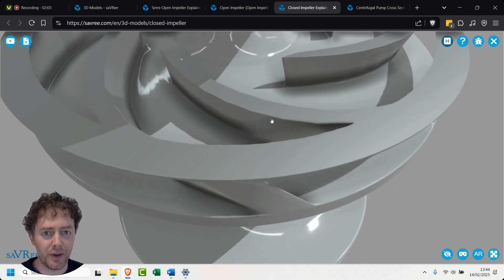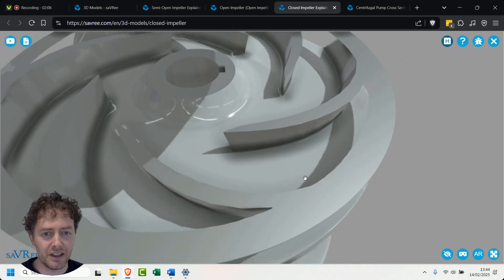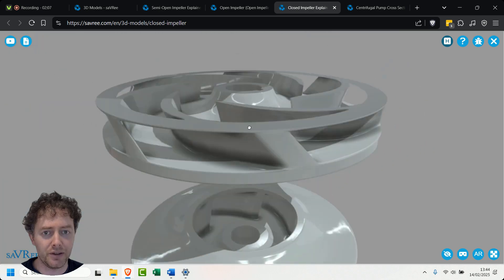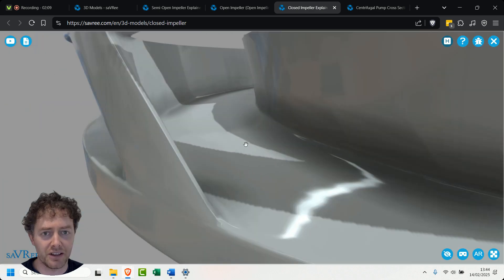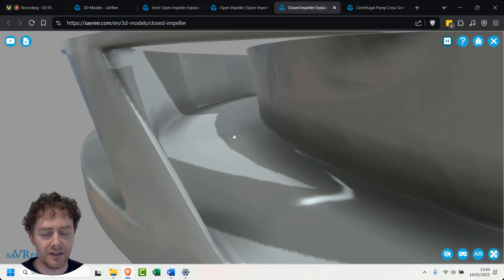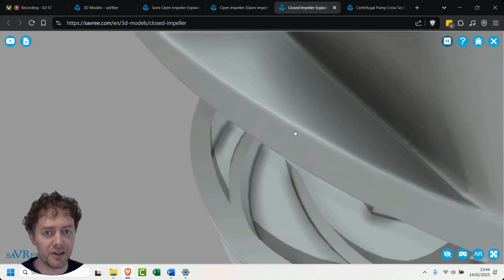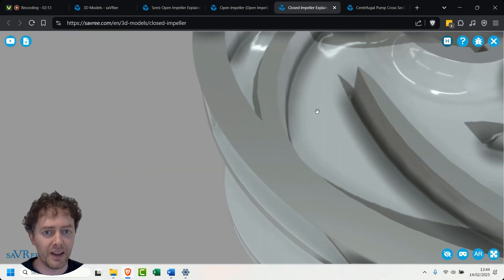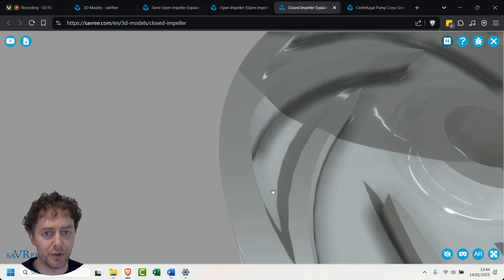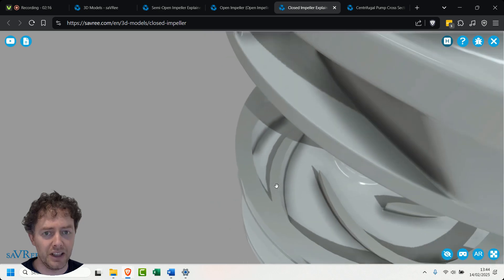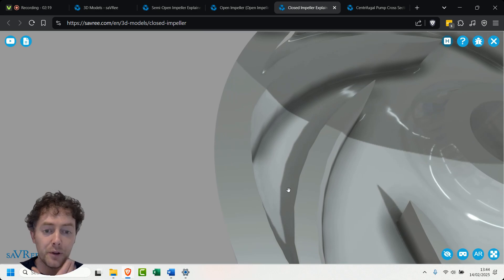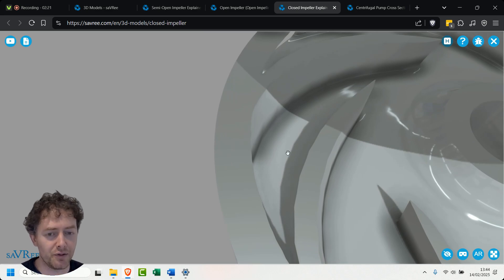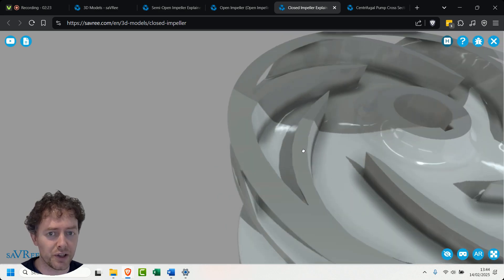In between the vanes we've got channels. This is the channel where my mouse is and the fluid or liquid is going to get sucked. In fact no it isn't. It's going to come into the middle and then it's going to be thrown out radially through these channels. Notice the channels get wider as they go outwards. That's because we're getting a velocity change, a velocity reduction and a pressure increase.